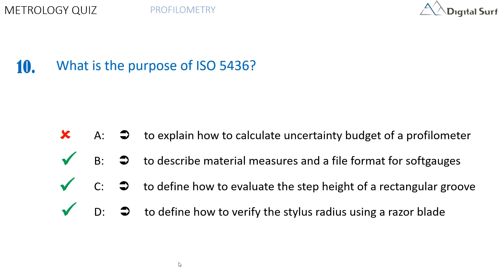The correct answers are B, C, and D. ISO 5436 is a standard that describes, in its first part, material measures used for the calibration of stylus profilometers. It includes material measures with steps or various types of grooves, and also describes how to evaluate the shape of the stylus tip using a razor blade. The second part of this standard defines soft gauges, which are files or reference programs used to validate software algorithms. The standard does not deal with uncertainties.